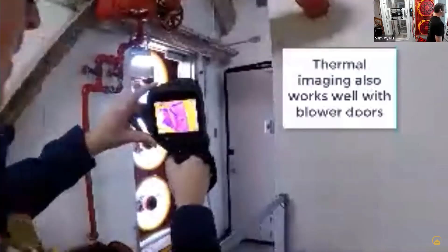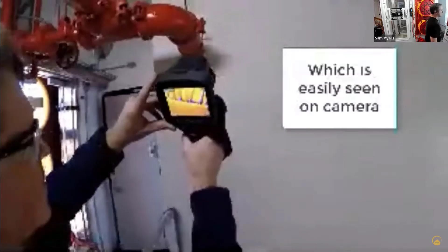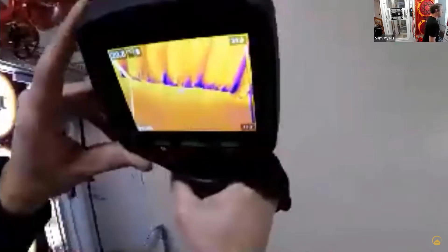And we were able to capture some good thermal images here too, where we're depressurizing the building, and then looking up, you can see the metal corrugated roof deck there. And there was some fiberglass insulation stuffed in. Maybe that was acceptable back in the 80s, but obviously it doesn't work very well. And so we can see that cold air coming in from there too. So with the major stuff, like the louvers and the elevators and the roof deck, it's kind of death by 1,000 paper cuts in this building. There was really no air barrier on it at all, so it just leaked like a sieve.